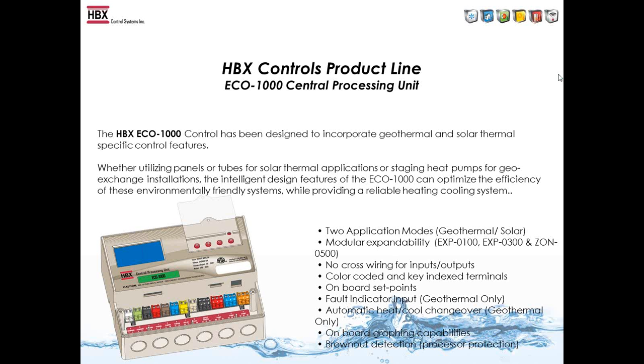So what that does is that we have a warm weather and cold weather shutdown built on, so you can adjust the settings so it doesn't matter if the thermostat is calling and cooling. If it's only 40 degrees out, you can lock those out. It has onboard graphing on the ECO control along with the brownout detection also.